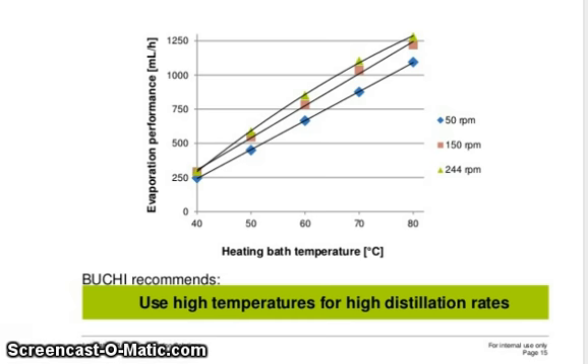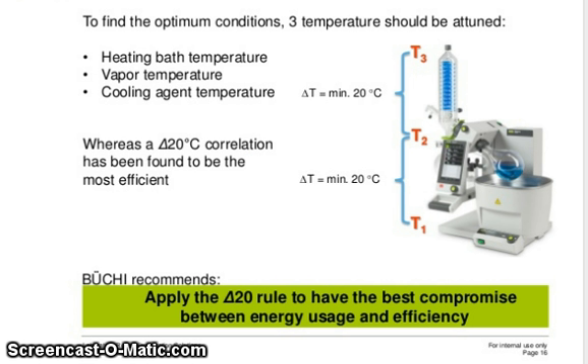Evaporation performance depends on heating bath temperature. You can see results at 50 RPM, 150 RPM, and 244 RPM — use high temperature for high distillation rate. To find the optimum conditions, three temperatures must be considered: heating bath temperature (T1), vapor temperature (T2), and cooling agent temperature (T3). A delta minimum of 20 degrees Celsius between each has been found to be most efficient.